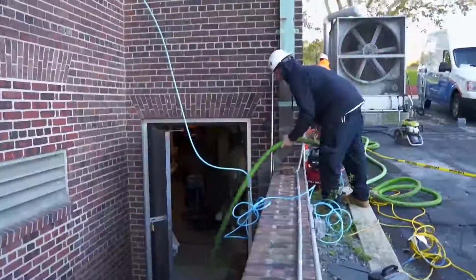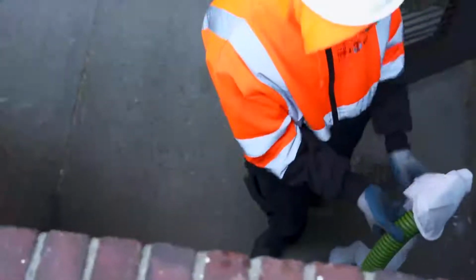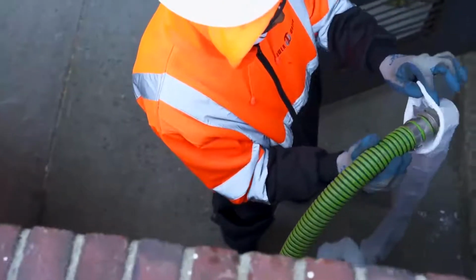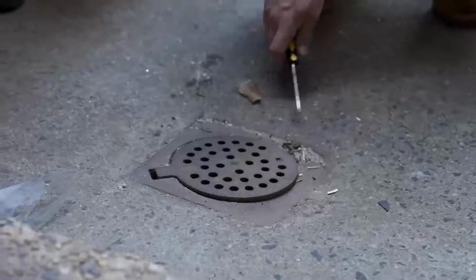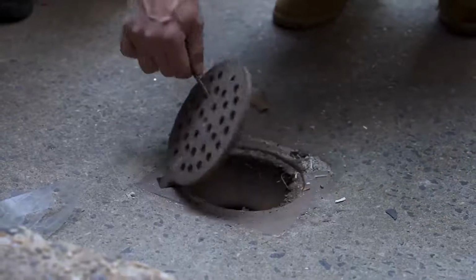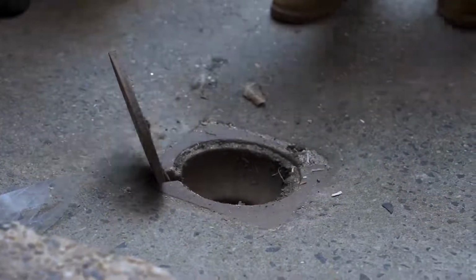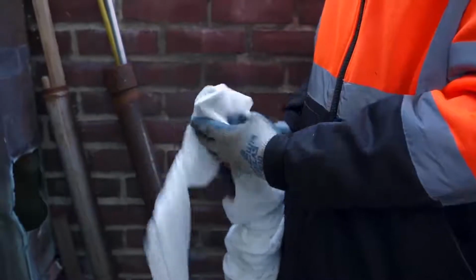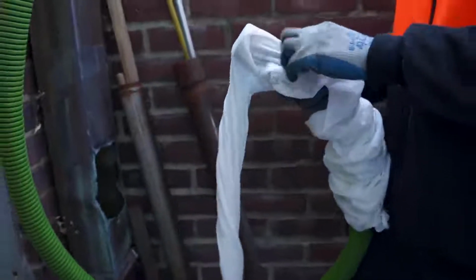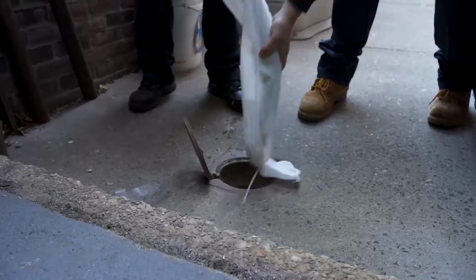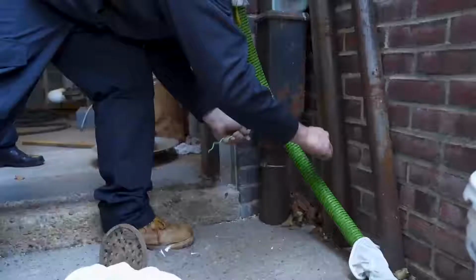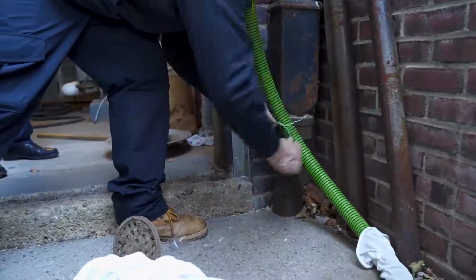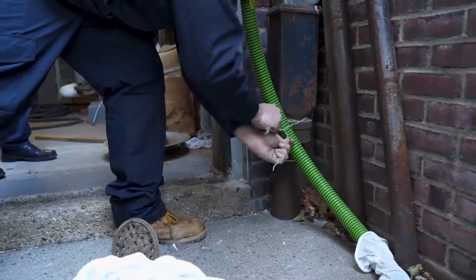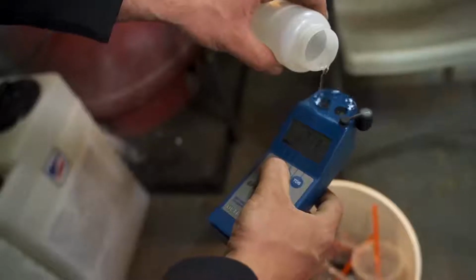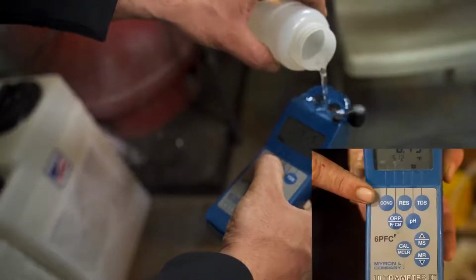Always make sure that the drain goes to sanitary sewer, as the cooling tower water cannot drain to the street. Always protect the drains so that no heavy dirt and debris goes down the drain, potentially causing a clog. Use the sock filter on the end of the drain hose to catch the large debris. Finally, secure all drains so that when you walk away from the hose, it will stay in the position as it was originally set.